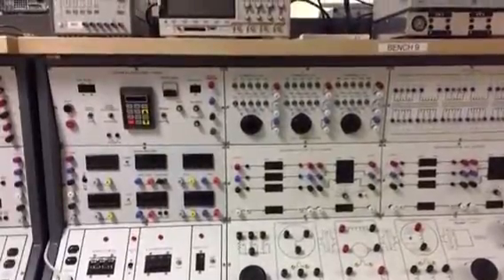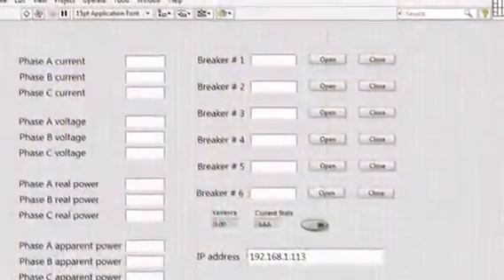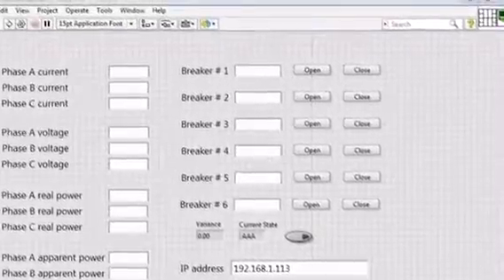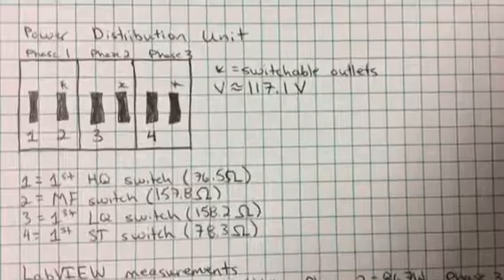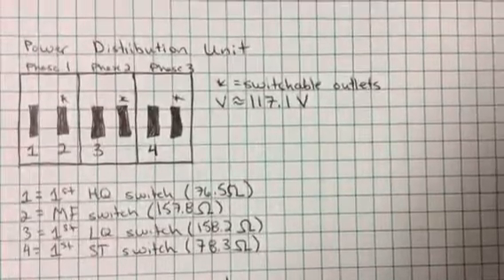The second preliminary step is to set up a test plan to evaluate the iterative load balancing solution provided by LabVIEW. Using the measured loads of the switch box, we can set up an unevenly balanced initial situation across the 3 phases of the PDU.